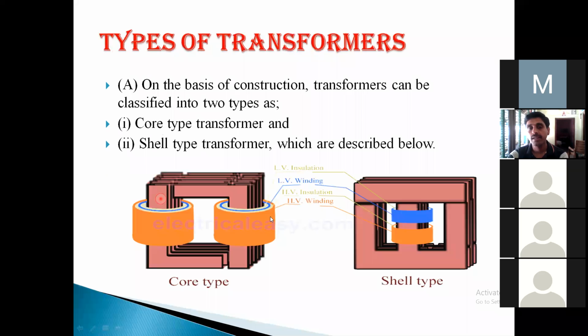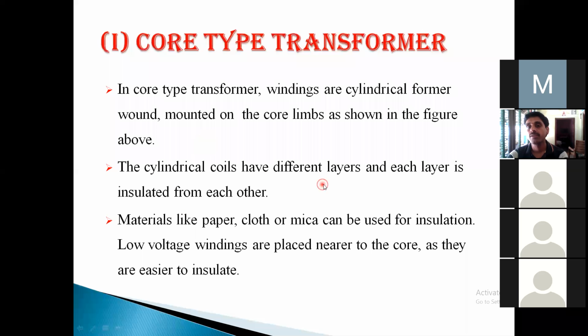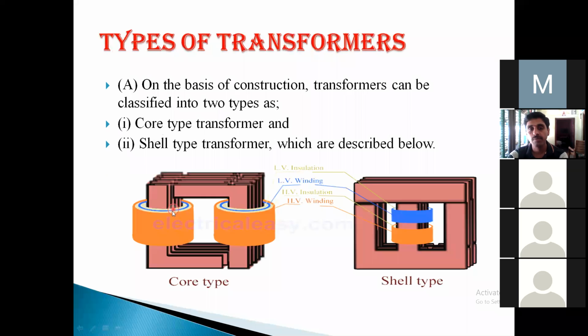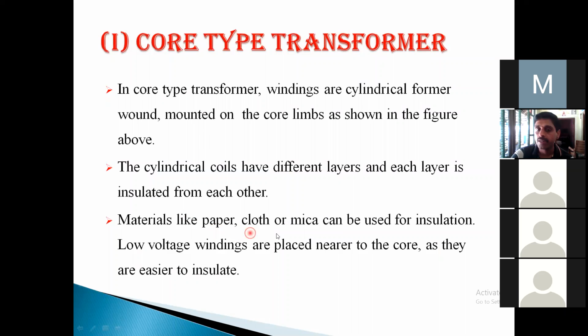Like this, windings are cylindrical, mounted on the core limbs. The cylindrical coils have different layers, and each layer is insulated from each other, because the number of layers will be, they are insulated from each other. And materials like paper, cloth, mica can be used for insulation.